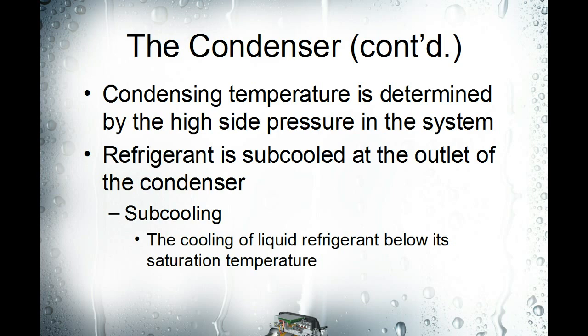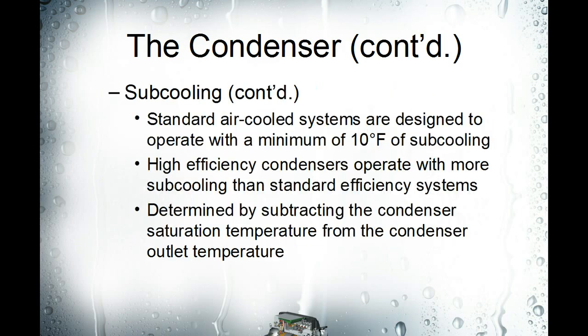Sub cooling occurs near the outlet of the condenser. Sub cooling is where we take the refrigerant that has been condensed from high temperature and pressure vapor down to high pressure liquid. Sub cooling ensures that we have completely released all of the sensible and latent heat and that we don't have any of the refrigerant boiling off before it hits the metering device.